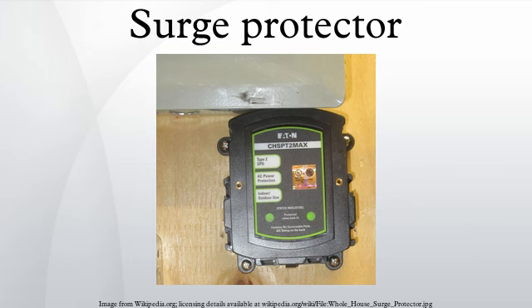GDTs take a relatively long time to trigger, permitting a higher voltage spike to pass through before the GDT conducts significant current. It is not uncommon for a GDT to let through pulses of 500 V or more of 100 nanoseconds in duration. In some cases, additional protective components are necessary to prevent damage to a protected load, caused by high-speed let-through voltage which occurs before the GDT begins to operate. GDTs create an effective short circuit when triggered, so that if any electrical energy is present, the GDT will short this. Once triggered, a GDT will continue conducting until all electric current sufficiently diminishes, and the gas discharge quenches.